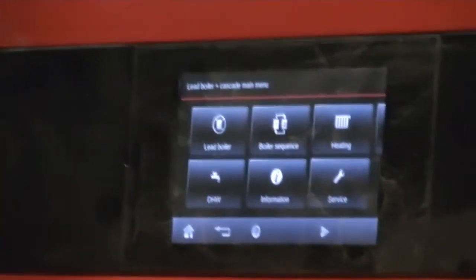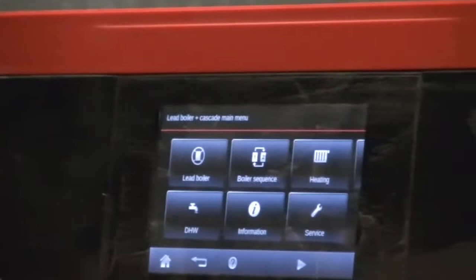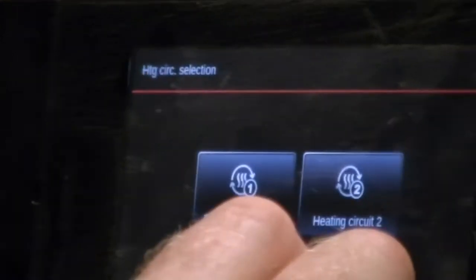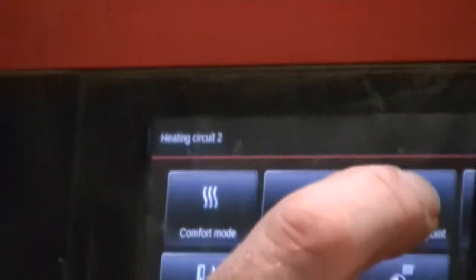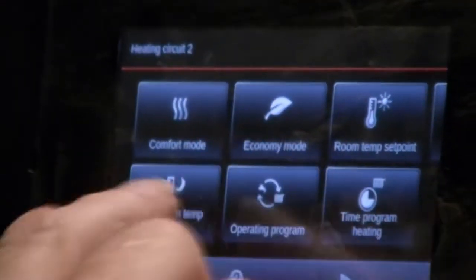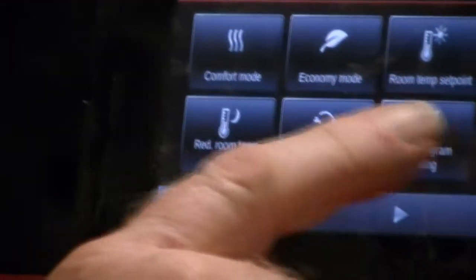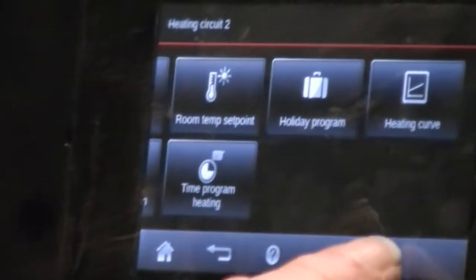Right. So if we want to adjust the heating curve, if we want to adjust the temperature of the heating, where would you think we would go? Yep. So for heating circuit number 2, it is your heating system. So let's say heating circuit 2, that's your fixed temperature. You should see something there that says heating curve. You may have to go over to the right, so you can see that right arrow here. Okay. So the heating curve button.